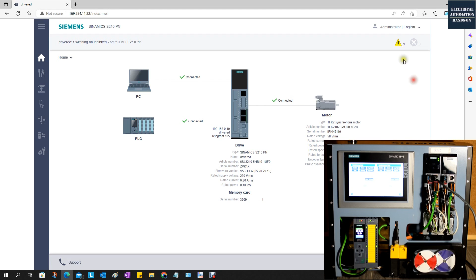And now we can firstly see the error or alarm showing here. We can see the fault. Okay, that's because it doesn't have the PROFIsafe configuration, which is fine. By default, the servo drive does not include the safety. So we can use the Webpage to spin the motor without any safety. So when you spin the motor, you need to be very careful.